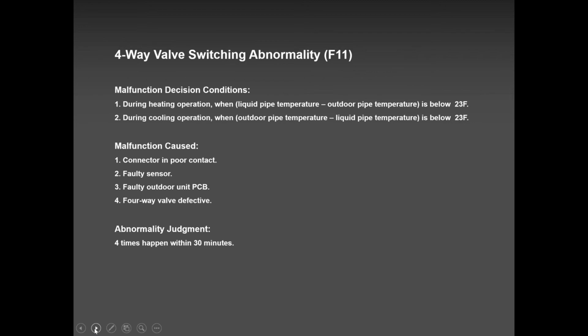Four-way valve happens, but very rare. If you get an F11 on a system that has been running for maybe 8-9 years, it's the indoor sensor. When it says faulty sensor, it's the indoor sensor that has a problem. Okay? And if it's on a brand new system, go outside and check. Chances are, during the power supply cable installation, when they were shoving in the wire, who knows? Sometimes the plug gets pulled off and it came off the four-way valve, and now the unit is not engaging.